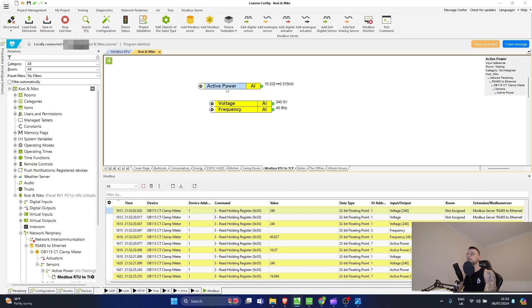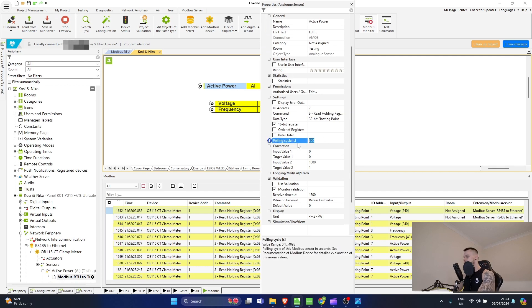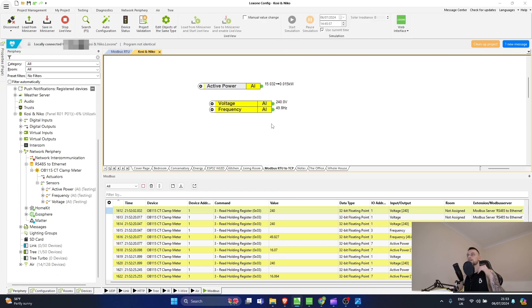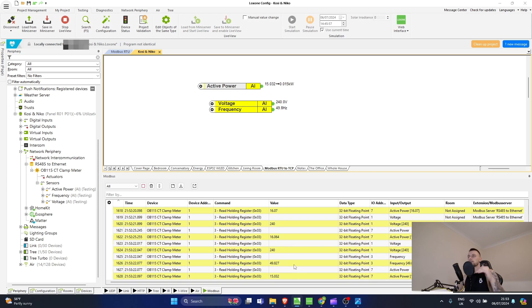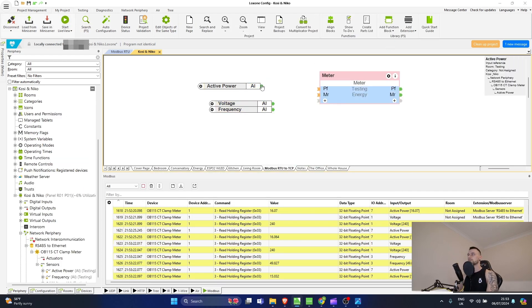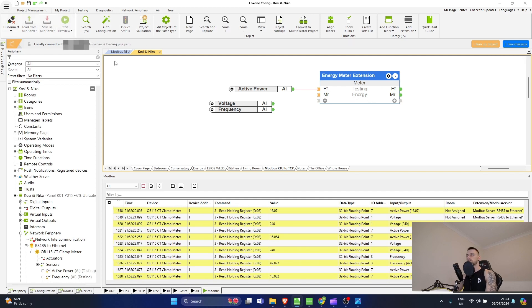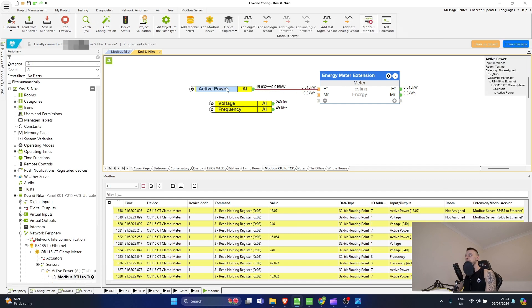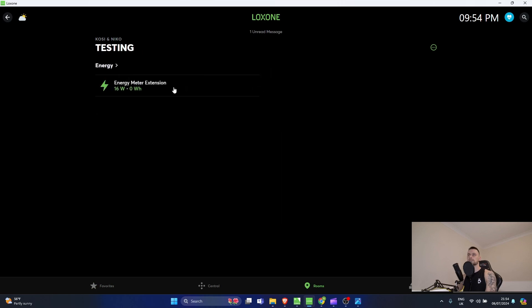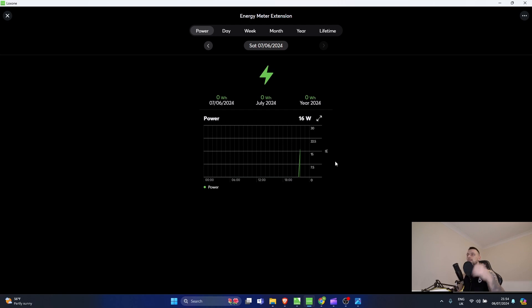After saving to the Mini Server, I can see 0.015 kilowatts. I also want to test the polling speed - can we get a reading every five seconds? Remember, all that traffic is on your local network, so you don't want to kill it with excessive Modbus TCP polling. I'll drop a meter on the page, name it 'Energy Meter Extension' for the connected devices - lights, phone charger, and a few other things. Saving it and checking the app, I've created a new room called Testing, and there it is: 16 watts in real time.